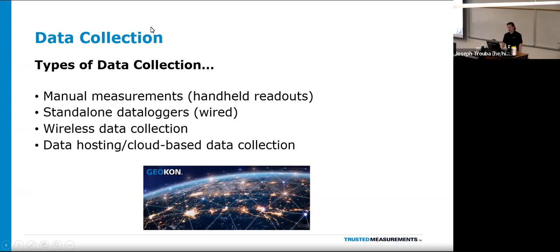So some types of data collection, I like to break it down into four different parts. You have your manual measurements, your handheld readouts, where you are physically going there, taking a measurement and recording it. We have standalone data loggers where the instruments are wired in, pre-programmed, and you come back periodically and download. We have wireless data collection, where an entire monitoring program can be collected and pushed to a single point where you can control the full network, download the full network from a single point, and then finally push it out to a cloud-based system or third-party software, things like that.